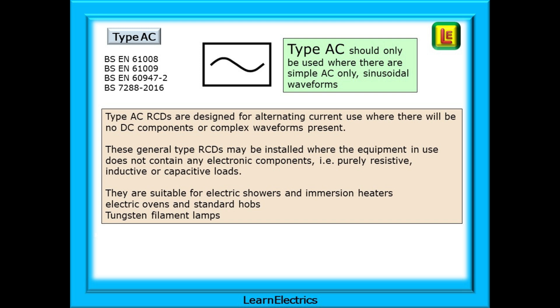Type AC RCDs are designed for alternating current where there will be no DC components or complex waveforms present. They may be installed where equipment does not contain any electronic components — in other words, purely resistive, inductive, or capacitive loads. They are suitable for appliances like electric showers, immersion heaters, electric ovens, standard kitchen hobs, and ideally suited to tungsten filament lamps — the old 60 watt and 100 watt lamps.